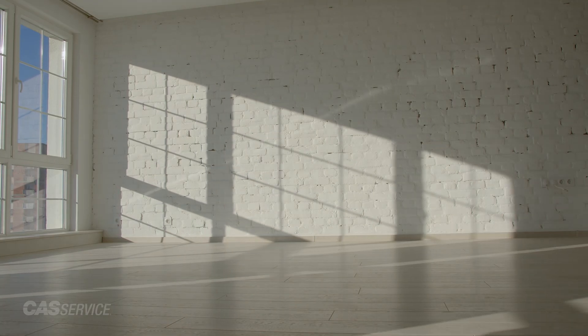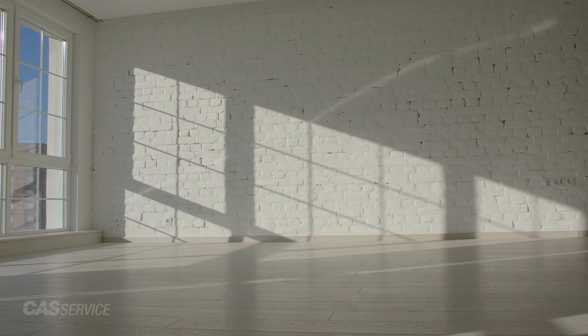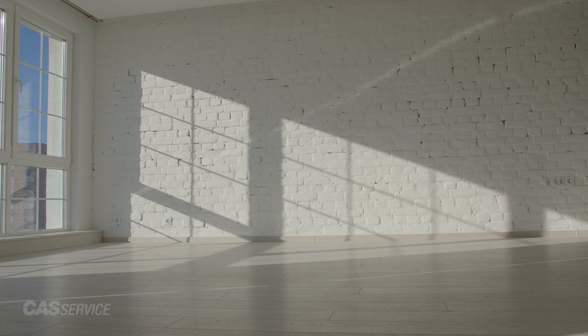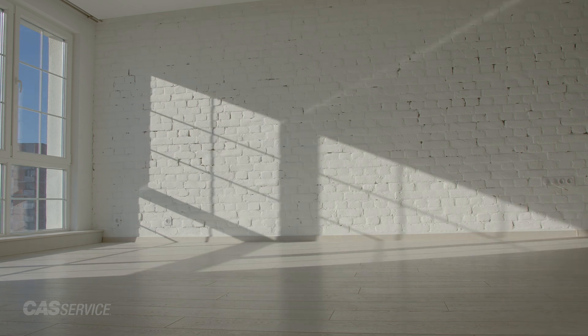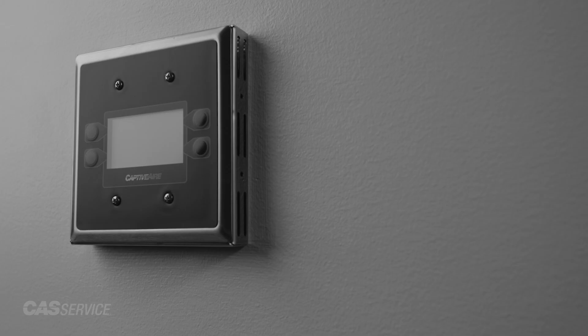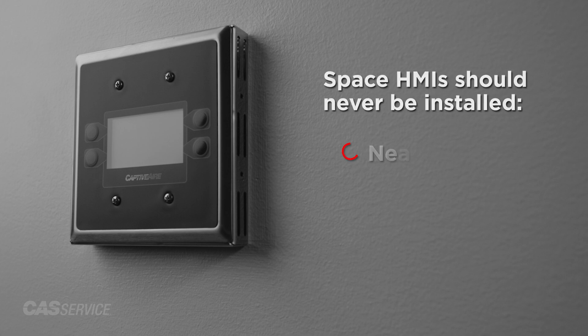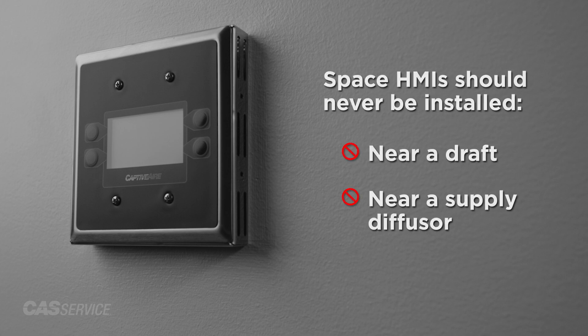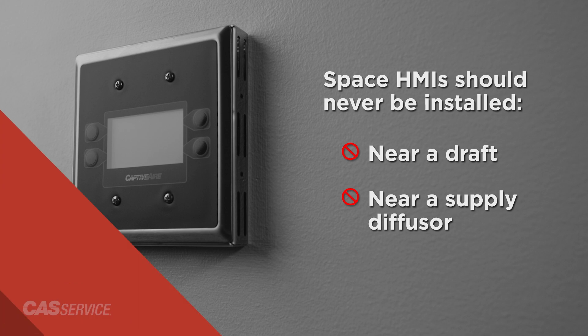We recommend space HMIs are located in a room not impacted by sunlight, while giving the best representation of average space conditions, typically near a return. Space HMIs should never be installed in an area with a draft or near a supply diffuser.